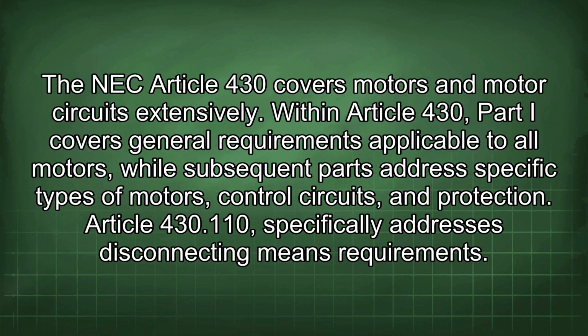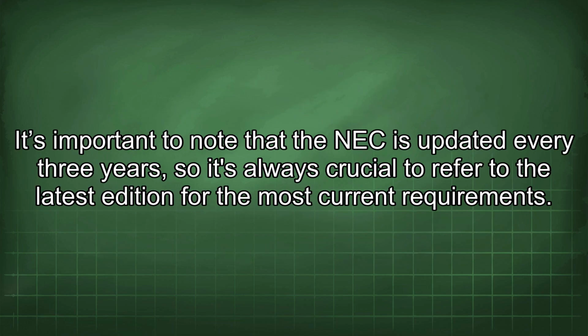The NEC Article 430 covers motors and motor circuits extensively. Within Article 430, Part I covers general requirements applicable to all motors, while subsequent parts address specific types of motors, control circuits, and protection. Article 430.110 specifically addresses disconnecting means requirements. It's important to note that the NEC is updated every 3 years, so it's always crucial to refer to the latest edition for the most current requirement.